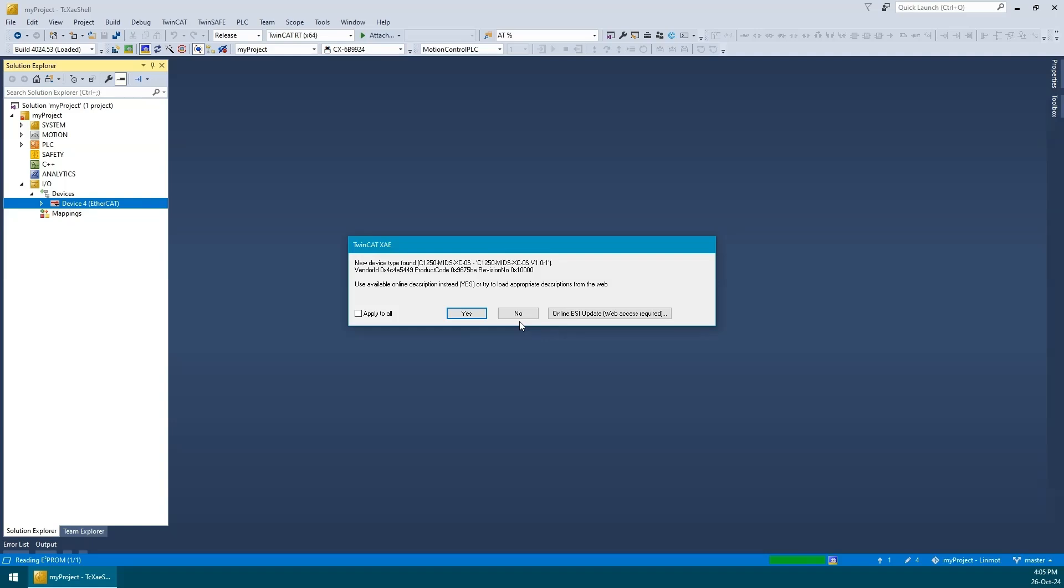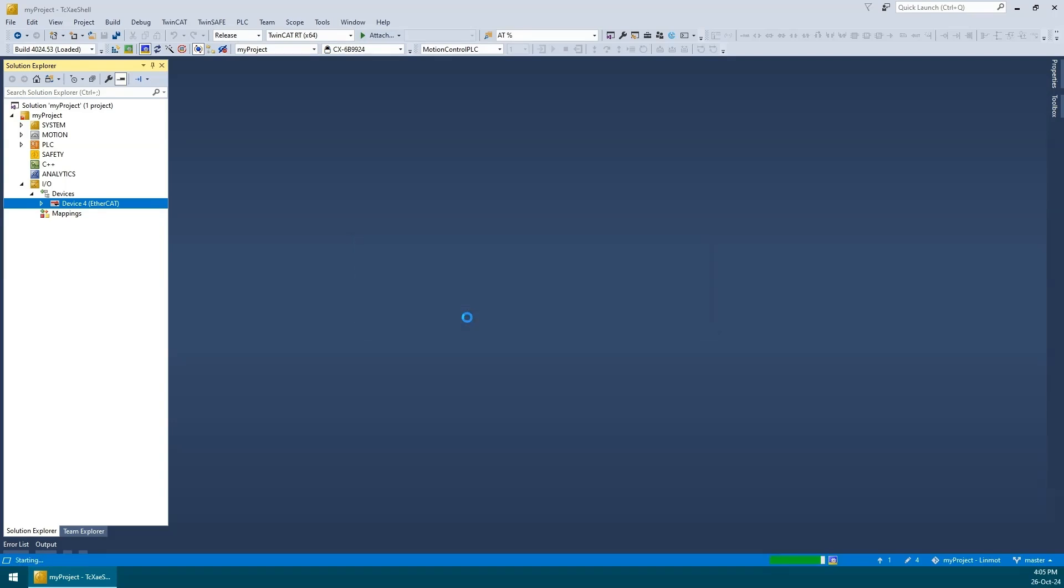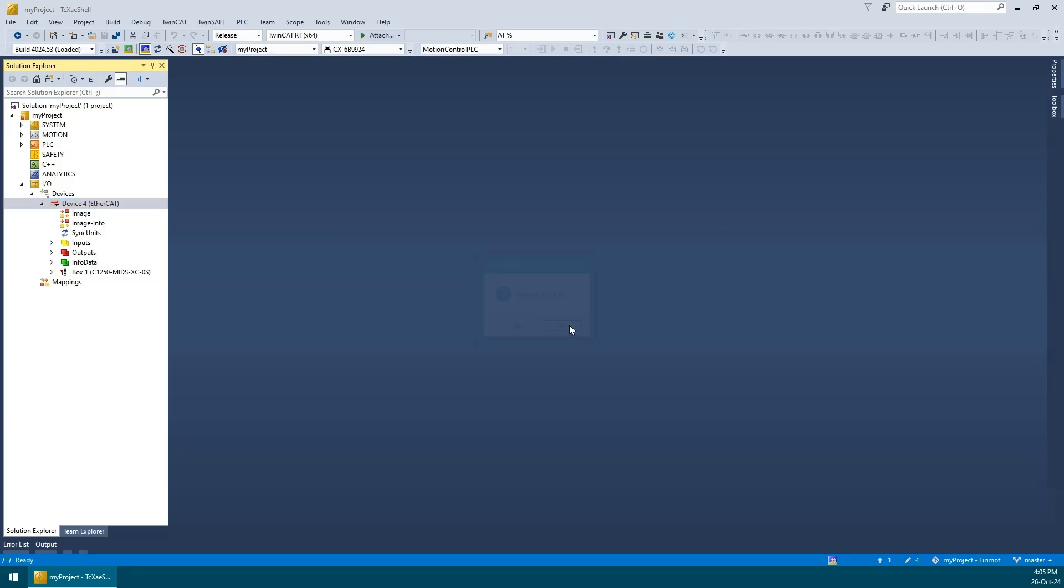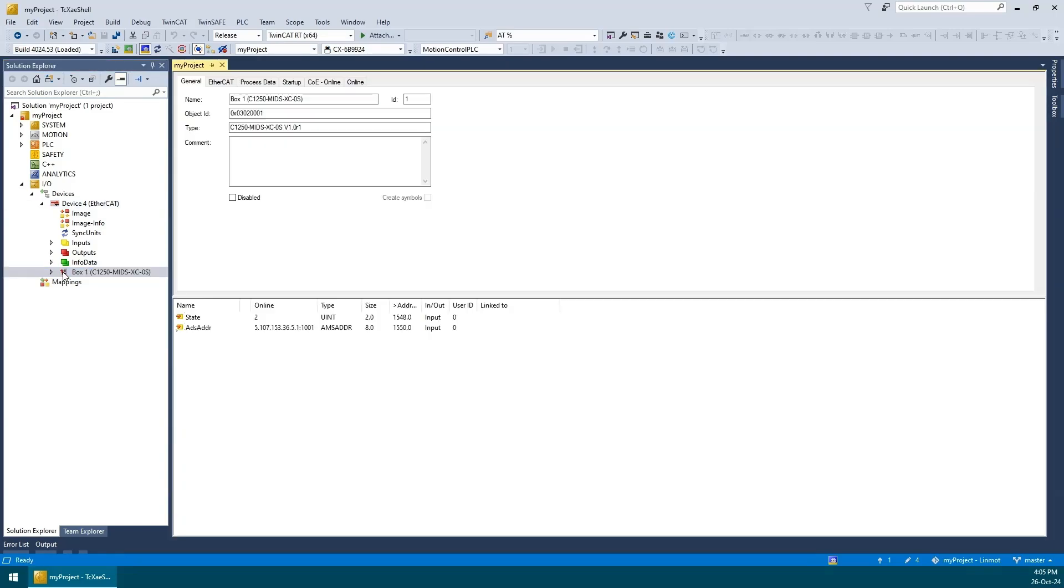Hmm, TwinCAT discovered the device but it doesn't have sufficient information about it and is asking if it should use the online description from the device EEPROM. Let's see what happens if we say yes. This doesn't look good. Notice the question mark next to the device and it named it as a box and doesn't recognize it as a drive.